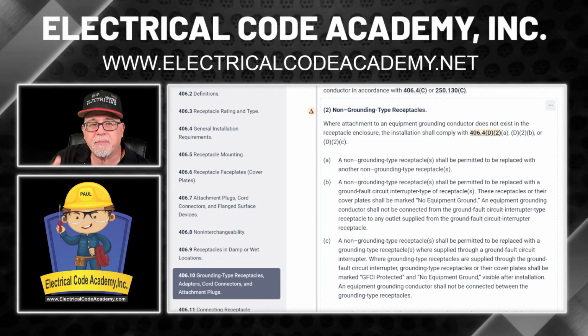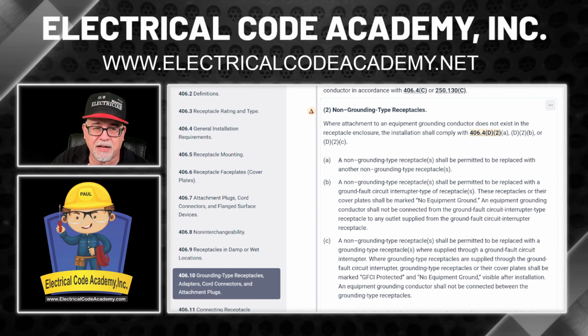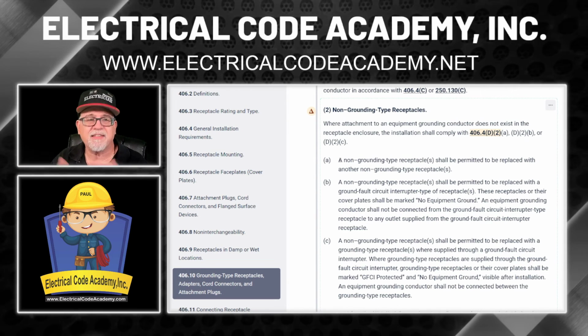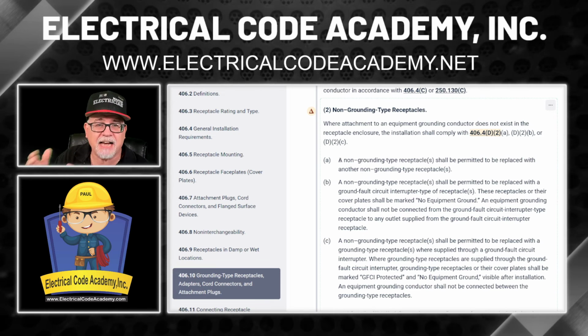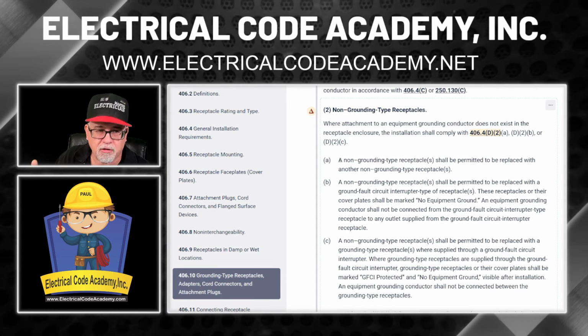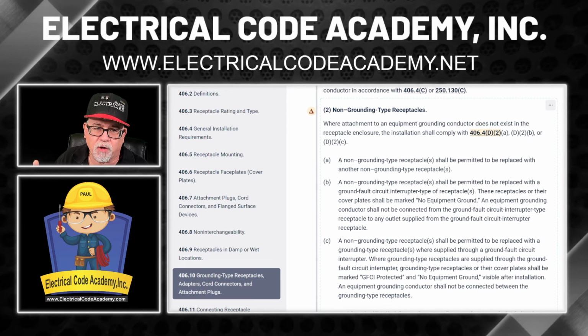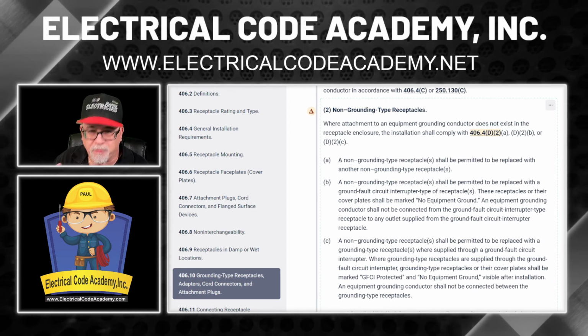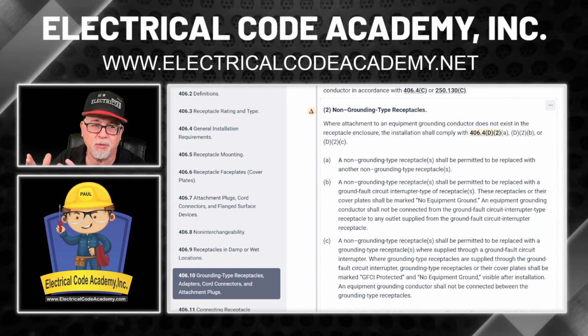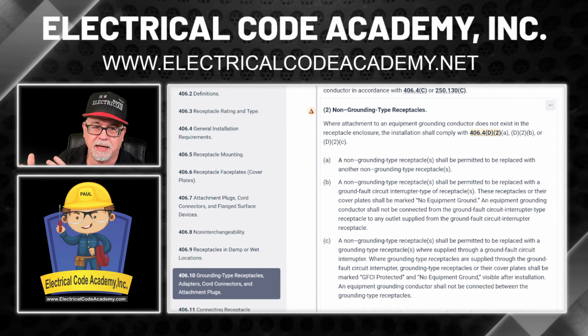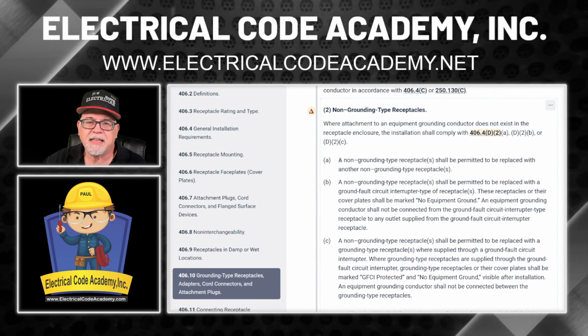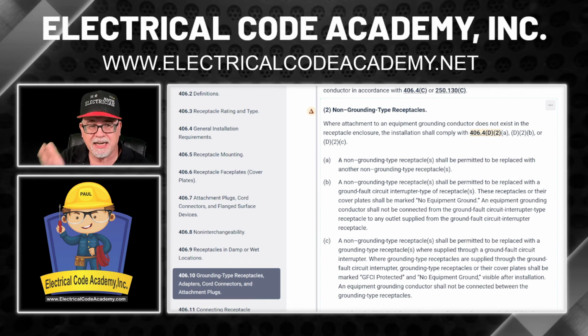So connecting anything beyond that to the green screw on it and going downstream to other receptacles would be misleading and it would be false because you're not going to be establishing an equipment ground, an effective low impedance ground fault current path. You're not going to be establishing it from the GFCI. It wasn't there to begin with. So you're just not going to use it. Okay. All right. So that's what he did. And he stopped right here.